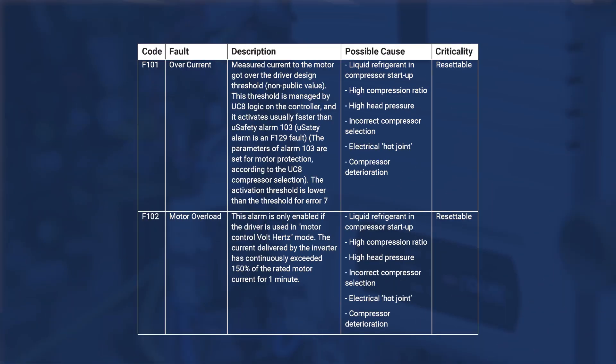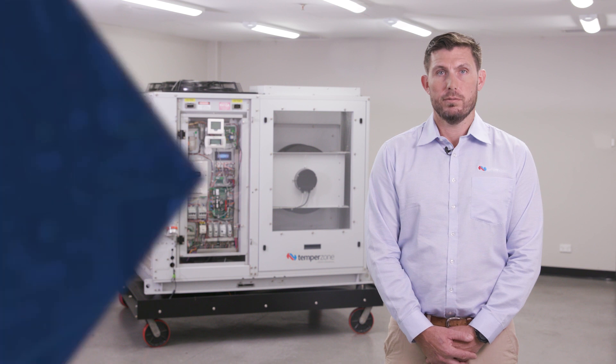If you find your Corel Power Plus in fault, cross-reference the fault code in the temperzone UC8 manual or temperzone Corel Power Plus manual to help your diagnosis. Just remember that more often than not, an inverter will fault due to operational abnormalities within the refrigeration system or power supply related issues, not a fault of the inverter itself. Some general checks that may help you with your inverter investigations are: check the UC8 display.